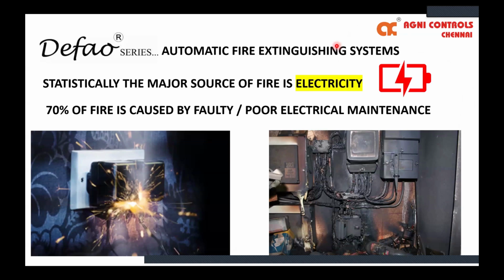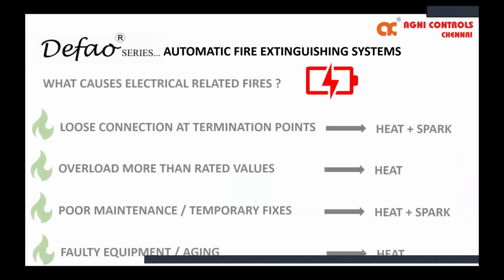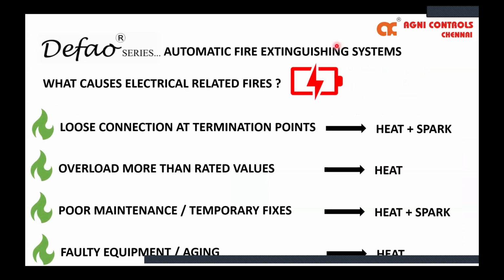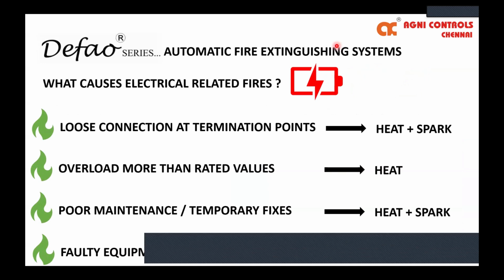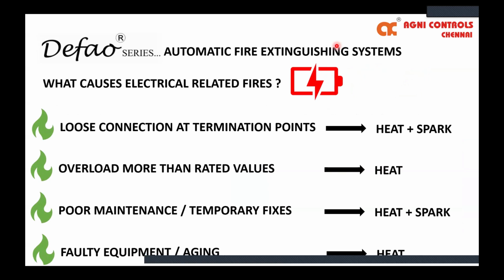As Mr. Dominic suggested in the initial briefing, as per the fire industry data, 70% of fires are caused by electrical failures. And what we are talking about, faulty or poor electrical maintenance, is that initially everything is perfectly designed. Over a period of time, the electrical load is abused by overrating load values, overloading more than the rated values, loose connections at the termination points, temporary fixes, tapping of extra wires, faulty equipment, and aging.